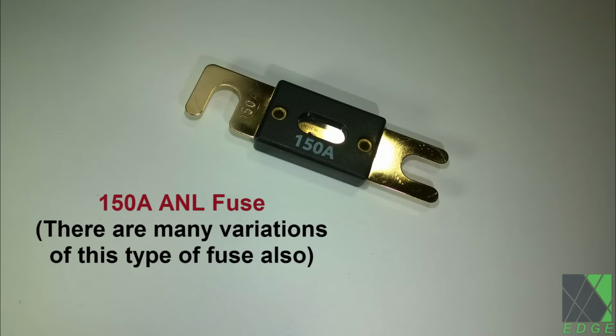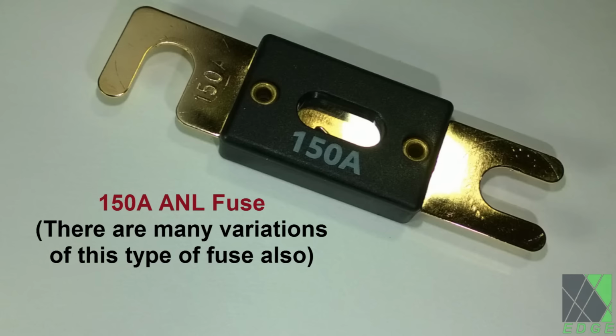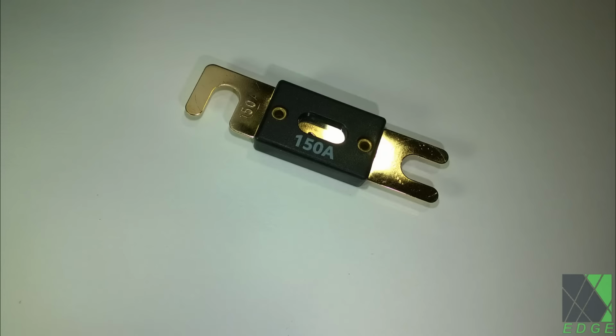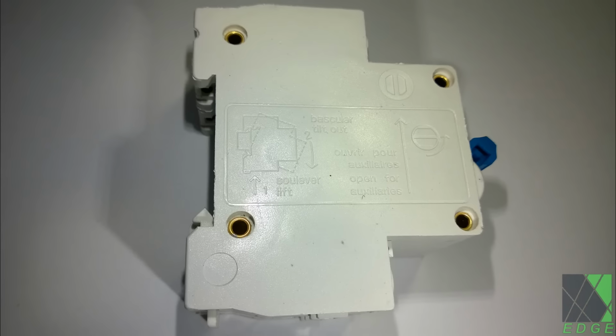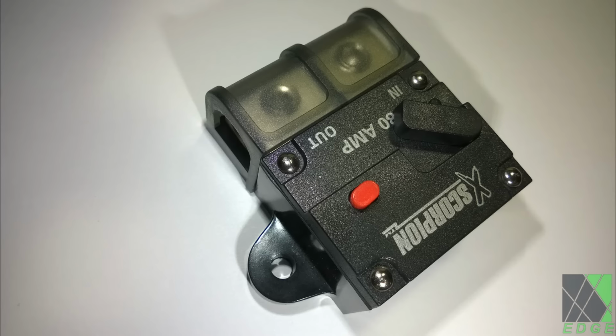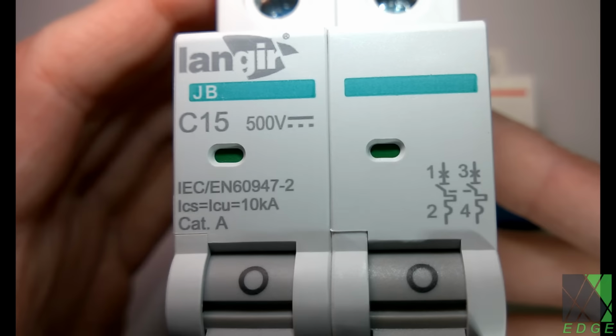Sometimes it's better to use an appropriate fuse, such as an ANL fuse, instead of a circuit breaker, as they generally have less resistance. And they too should be kept as cool as possible for the same reasons as circuit breakers. The reason is, depending on its design, if the fuse or circuit breaker is in an unusually hot environment, it may not perform as intended and may trip at a lower rating than it's supposed to.